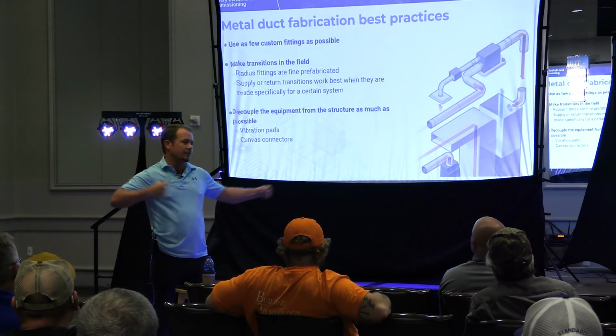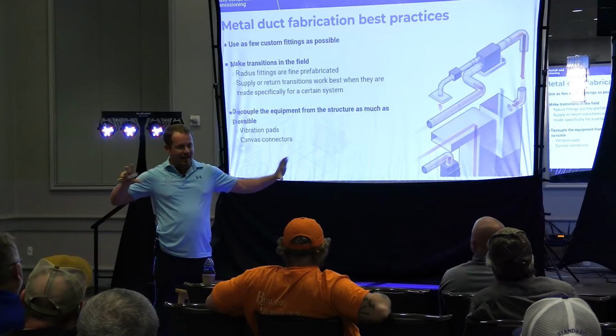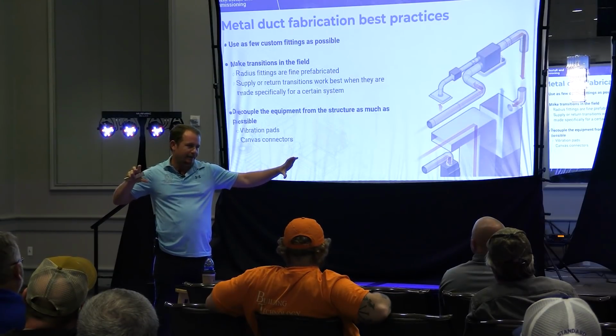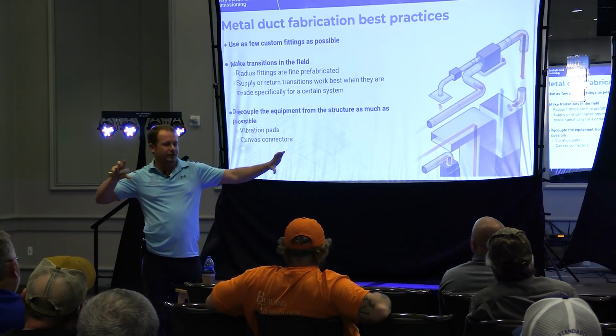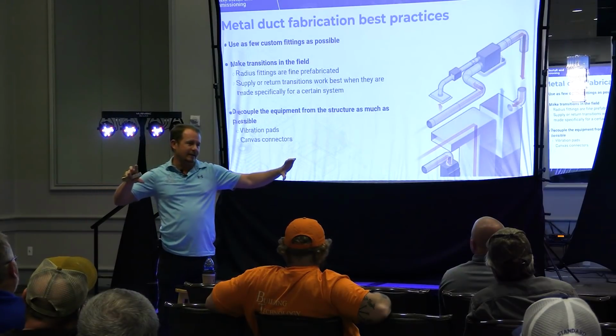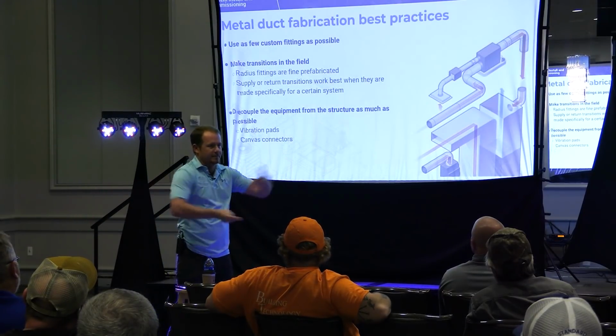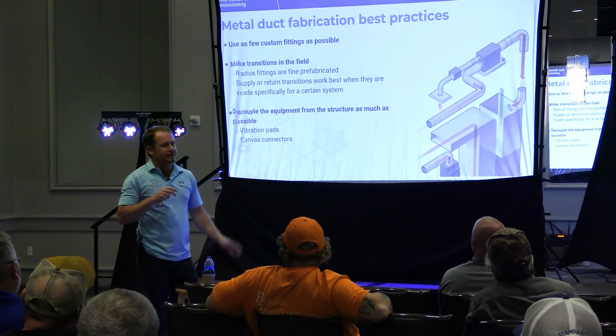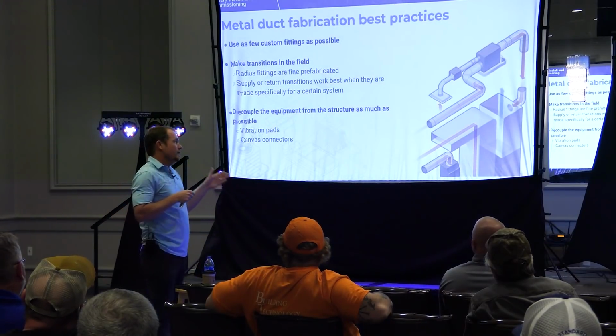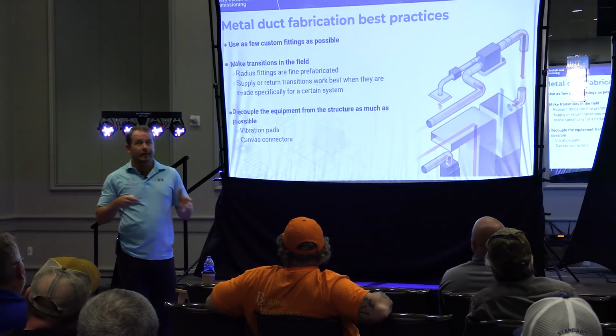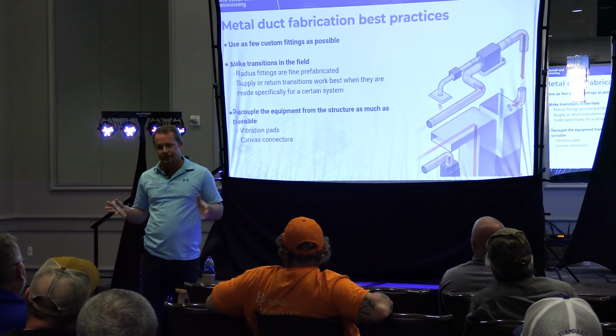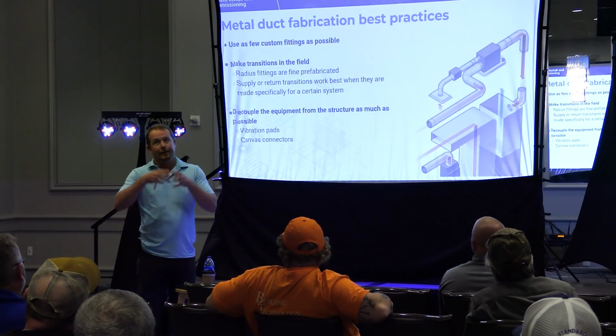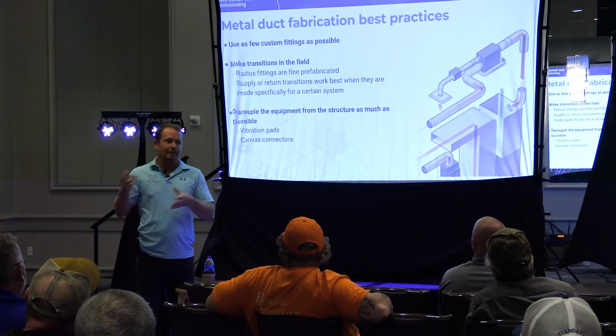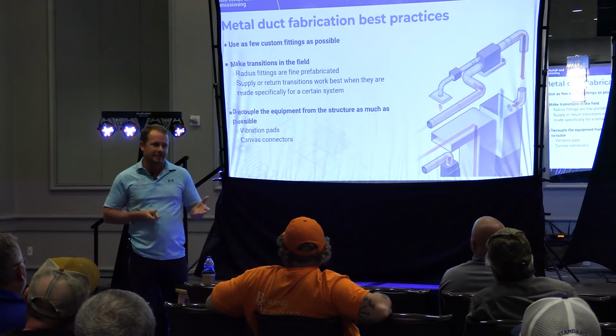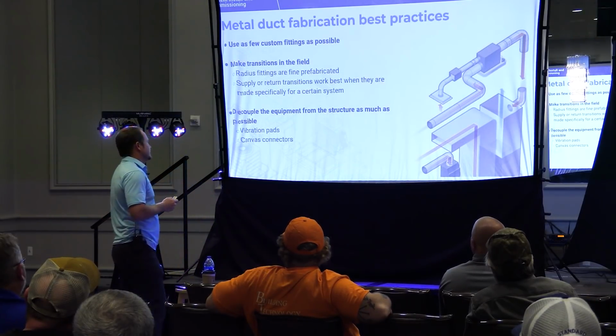If you take flex and you pull it really tight, at least in that area, you're not going to have leaks and your friction isn't going to be that great. The downside to flex is people just use it to make everything and they don't fully extend it, and so now it becomes a friction rate issue. With metal, it's not so much a friction rate issue. Again, if it's sized properly, it's much more of a leakage challenge. So doing things like actually masticing it, letting it dry before you insulate it, those are things that get missed sometimes. So those are the things to focus on.